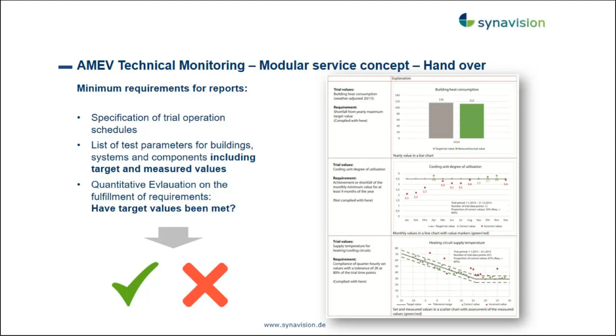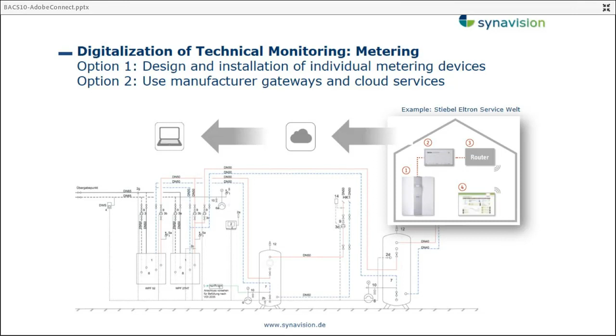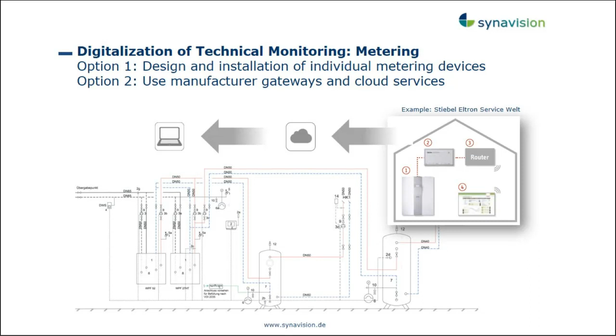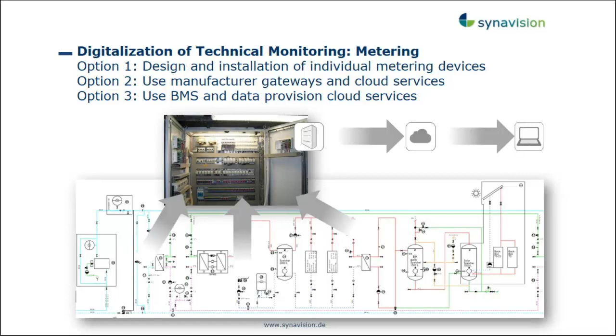Getting data out of buildings today is quite simple. Even in small buildings, you can design and install individual metering devices, but I think for the future this will not be necessary and way too costly. I think it will be much easier to use manufacturer gateways, for example for CHP or chillers or boilers. Many manufacturers already provide gateways that give you a lot of data from the individual systems. And of course you can use BACS - building management systems, building automation and control systems - that can also provide all this data. All these systems are capable of it, and the only thing that's really important is that this is in the tender documents, so it's part of the contractor's service.